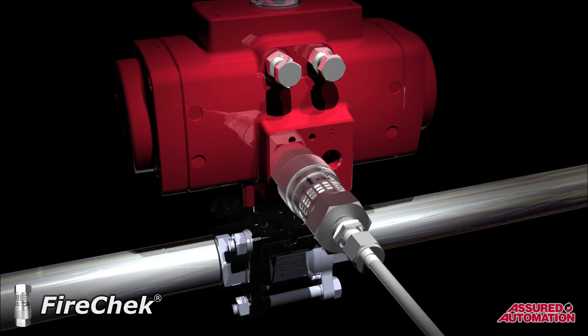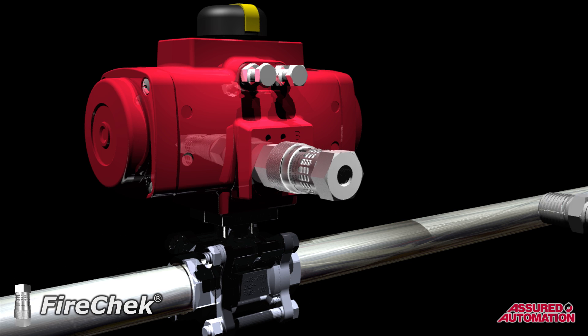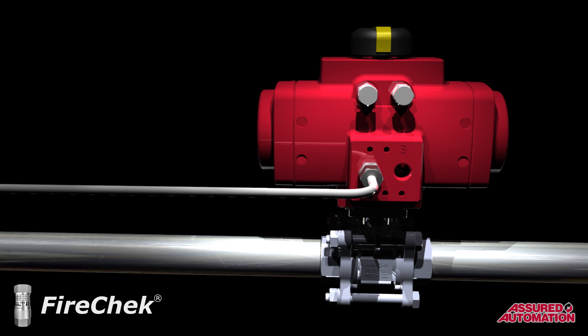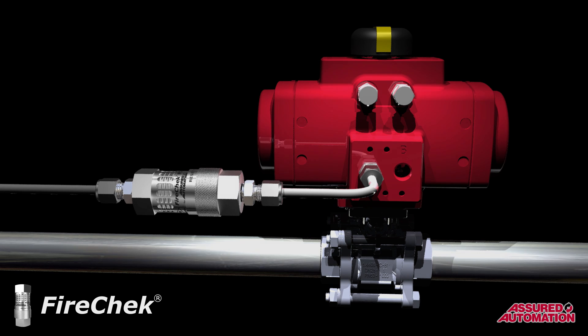When using the FireChek valve by itself on smaller actuators, installation is as simple as connecting the FireChek valve in-line on the supply air to the actuator. The FireChek valve can be nippled directly into the actuator port or installed anywhere upstream. Using two compression fittings makes for an extremely easy retrofit into stainless steel tubing. The FireChek valve can be located either before or after the actuator's control solenoid.